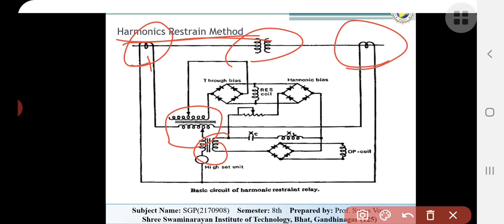Here it consists of a series of LC filters. You can see the LC filters, which allow only the fundamental component to flow through the operating coil and divert the high harmonics and the DC component. The sum of the fundamental and the harmonic components, with the inrush current having the high harmonic content, gives more restraining torque, and the relay remains inoperative for the magnetizing currents. So these are the operating systems, with coils to remove the inrush current.